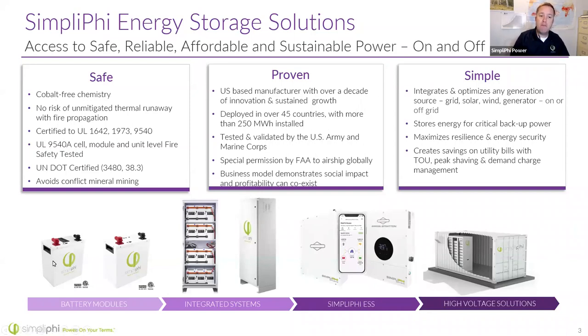That first battery integrates really well - it's a great drop-in lead acid battery replacement. Walking around Intersolar, I noticed so many different inverters capable of working with our batteries. Our batteries are inverter agnostic - that battery can work with your Morningstars, your Outbacks, your Schneiders, the Victrons, the Samlex, you name it, we've got a battery that will work with it, as long as you program that equipment to treat our batteries properly, like low battery cutout voltages, the floats, and the absorb voltages.